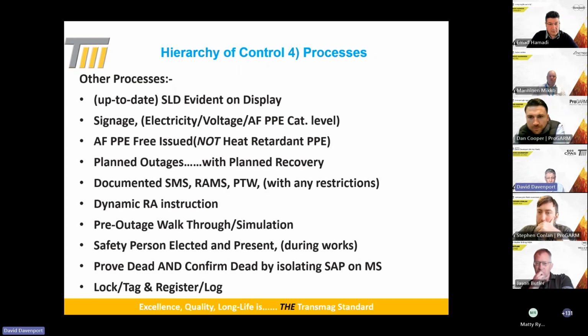The signage, does it actually state on the signage of your switchboard what the calories per centimetre squared is, and what category Arc Flash PPE is recommended? It should do. Arc Flash PPE should be free issued by employers, and it shouldn't be just heat retardant PPE, it should be Arc Flash PPE.